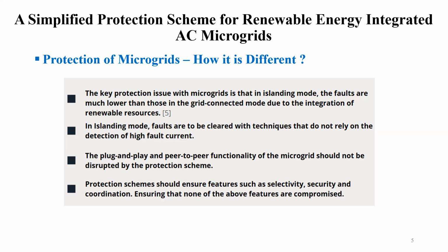So if there are 2 or 3 microgrids connected with a centralized network, what happens if there is a fault on the main line of a microgrid? That fault must not disrupt the operations of the centralized facility, as well as the other microgrids that are connected. Similarly, protection schemes should ensure features such as selectivity, security, and coordination, ensuring that none of the above features are compromised. So these are the things that are primarily required for developing the protection scheme for microgrids.